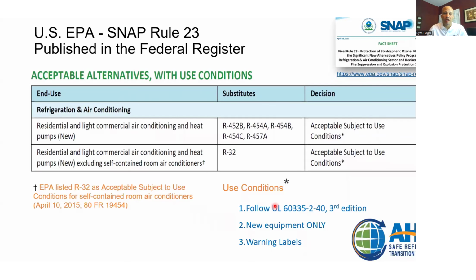All right, so all the HFCs we're losing from an HVAC perspective. So 407C, 134A, 410A, and all those favorites are going away. They're being replaced with new refrigerants. If you're not aware, the EPA has this thing called the SNAP rule. The SNAP rule defines all the various refrigerants that can be used for various kinds of applications.